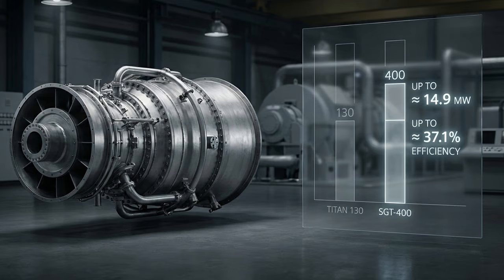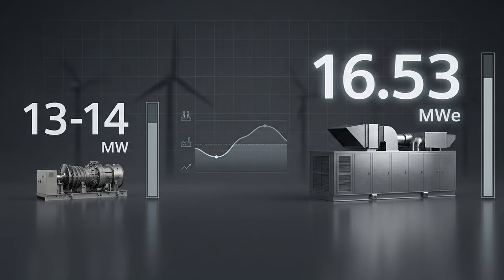The Siemens Energy SGT400 is a different power class candidate. Published mechanical drive output is up to approximately 14.9 megawatts, with efficiency up to approximately 37.1%. That is below the Titan 130 nominal mechanical drive rating, so application matching is essential. For power generation, the SGT400 is generally in the approximately 13 to 14 megawatt class, depending on version. That is below the Titan 130 generator rating, so engineers must compare installed capacity with the site electrical load profile.